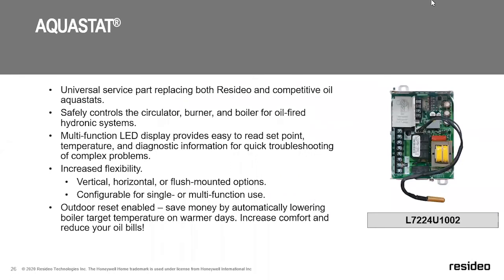While we're talking about oil products for oil installations, let's talk about our L7224U oil AQUASTAT. It's another universal part designed to replace a multitude of OEMs, whether they be Resideo or Honeywell Homes OEM products or competitive models. The nice thing about this controller is that it's super easy to program. It's got an LED display, which you use to program your set points. You can use it to adjust your high and low limit differentials. Maybe if you only have a high limit, you can make it just a high limit.